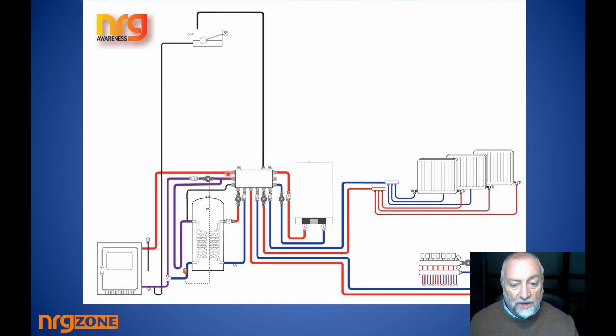So when it gets to this point, if it tries to go through the pump, there's a non-return valve, so there's a resistance. It's not going to be able to flow there. But if it takes down through the center of this T, it's falling down, it's trying to get back to the stove, but on the way down there's a heat lock loop.